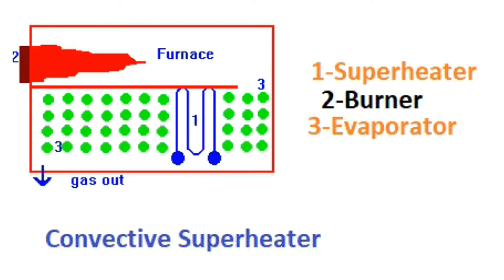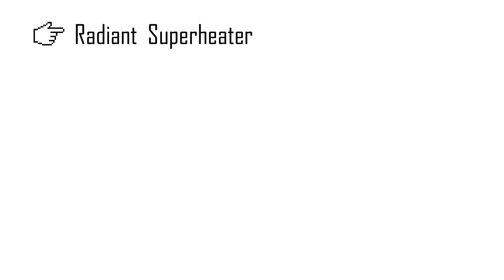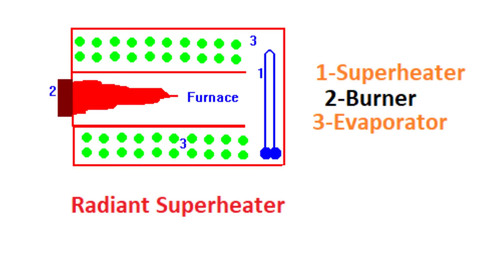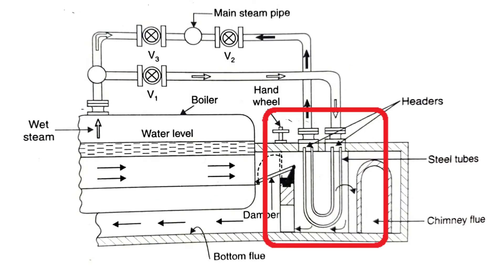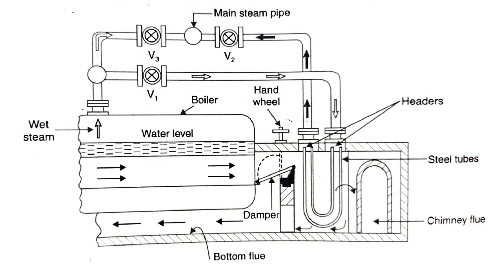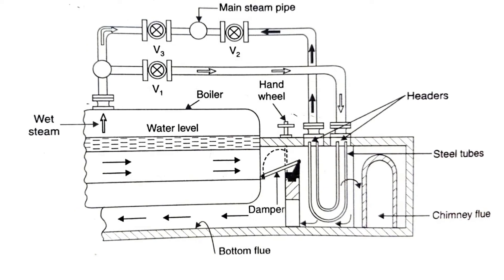A convective superheater makes use of heat in flue gases, whereas a radiant superheater is placed in the furnace and its tubes receive heat from the burning fuel through a radiant process. The radiant type of superheater is generally used where a high amount of superheat temperature is required. It consists of steel headers to which are attached solid drawn U-tubes of steel.